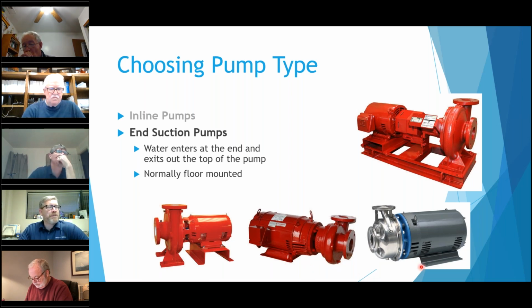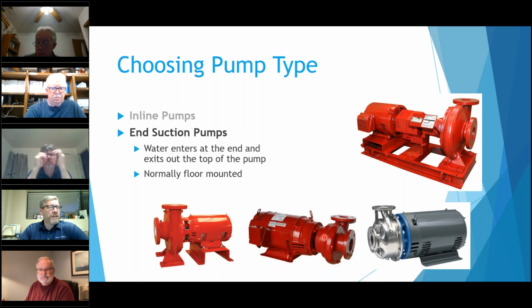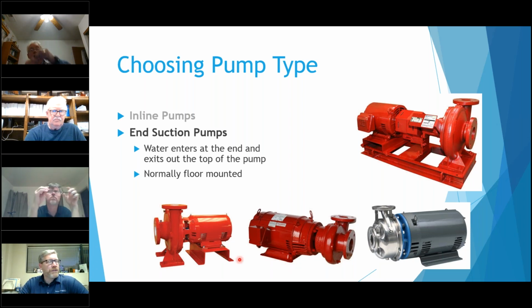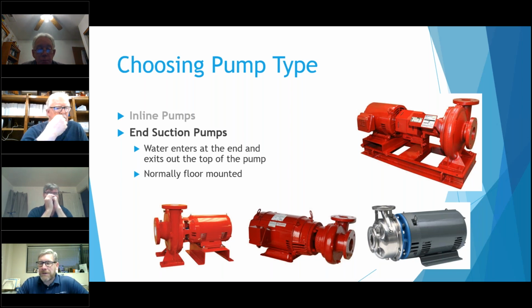Actually, I ran into an application yesterday with these end suction pumps, and it reminded me of one that happened a long time ago. You should use cap screws on these types of pumps, especially the motor mounted ones, so you can get the pump out of there to replace the seal. On the installation I was reminded of, they actually used threaded rod, and you couldn't get the pump out if the threaded rod didn't come out, and it was so long that it hit the motor. We had to eventually just keep cutting it out as we pulled it out. So it was kind of difficult, but you should use some type of cap screws on these. Obviously, on these where you've got your own little base, or even this one here, threaded rod will certainly work there.